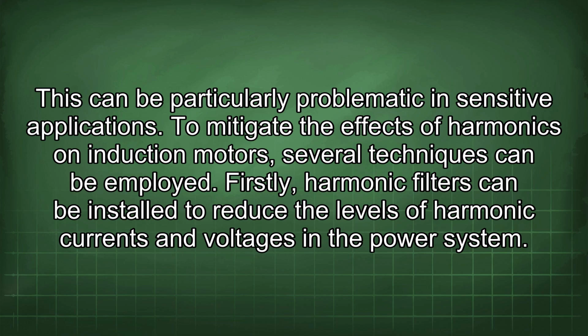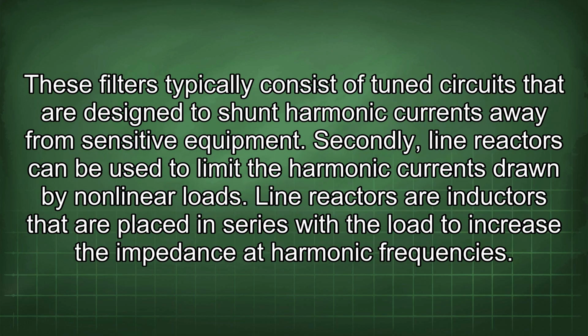To mitigate the effects of harmonics on induction motors, several techniques can be employed. Firstly, harmonic filters can be installed to reduce the levels of harmonic currents and voltages in the power system. These filters typically consist of tuned circuits that are designed to shunt harmonic currents away from sensitive equipment. Secondly, line reactors can be used to limit the harmonic currents drawn by nonlinear loads. Line reactors are inductors that are placed in series with the load to increase the impedance at harmonic frequencies.